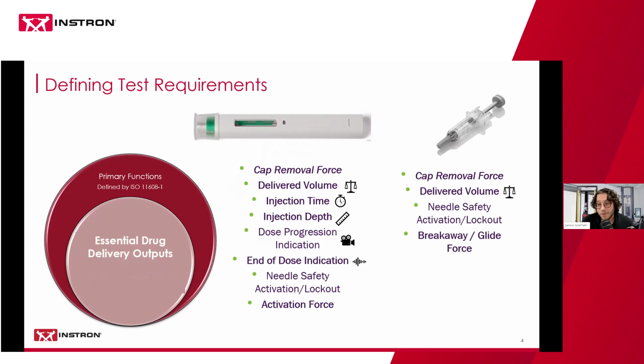And actually on essential performance requirements, we've been waiting for a number of years from the FDA on formal guidance. In the last month, they released their draft guidance, and actually decided to change the name to Essential Drug Delivery Outputs, but essentially the same thing in terms of what they're referring to. So these are the absolute critical design outputs that have to be tested to ensure the efficacy of the device. I have those bolded here. So the main ones are going to be cap removal force, delivered volume, injection time, injection depth, progression of the dose, end of dose indication, needle safety, and then activation force.